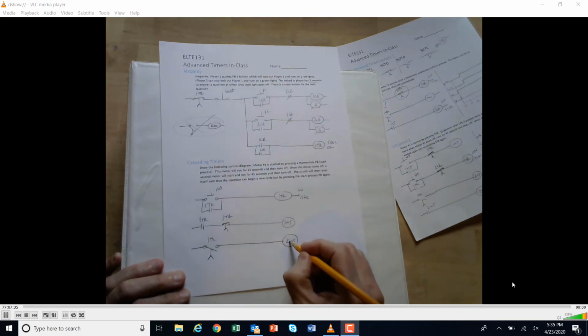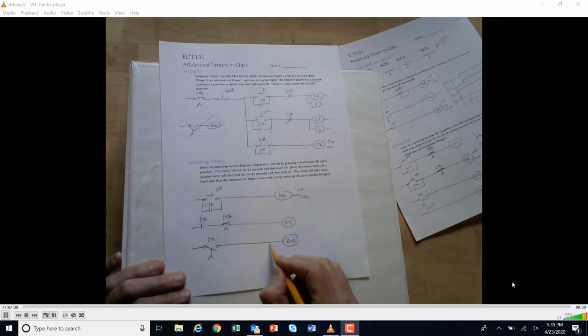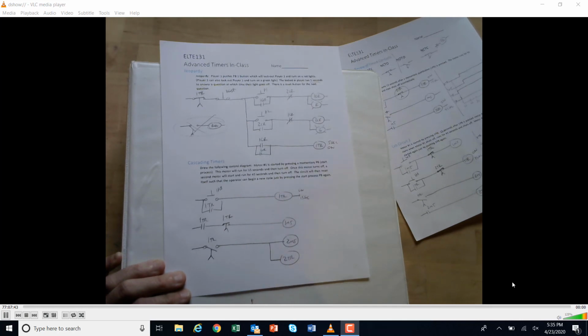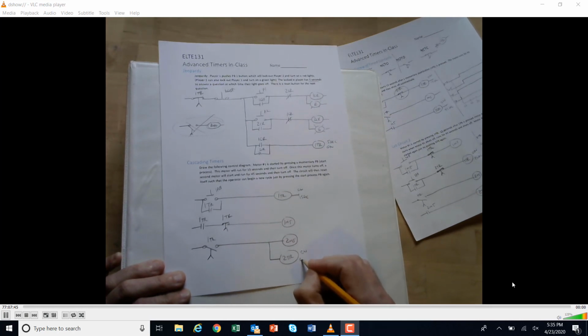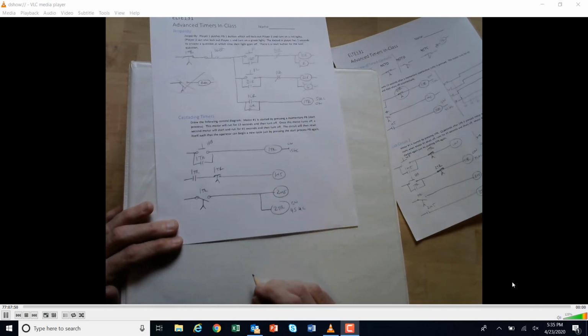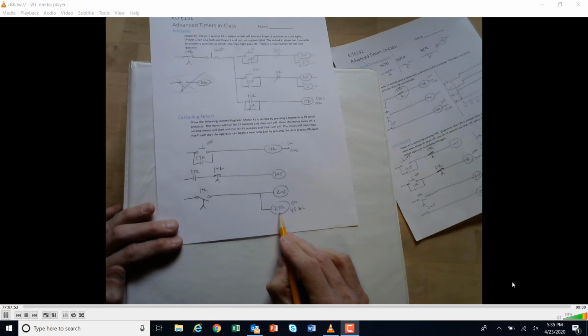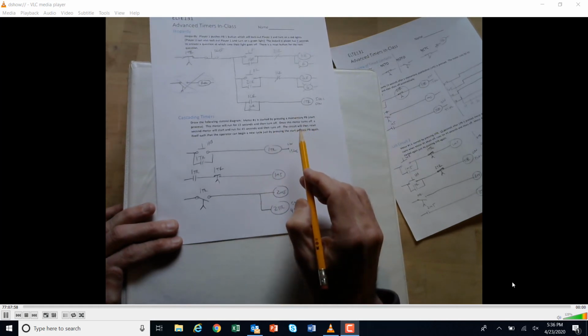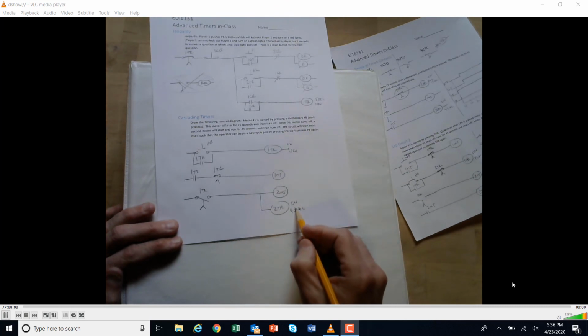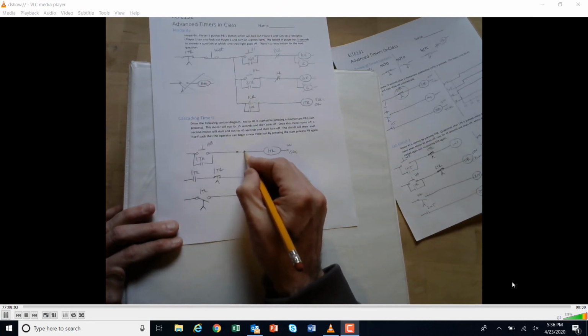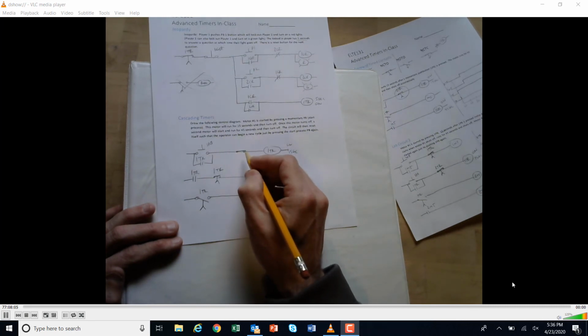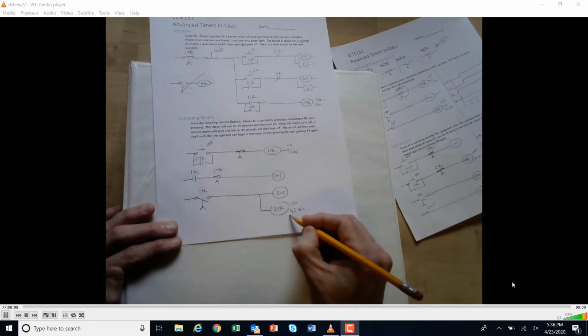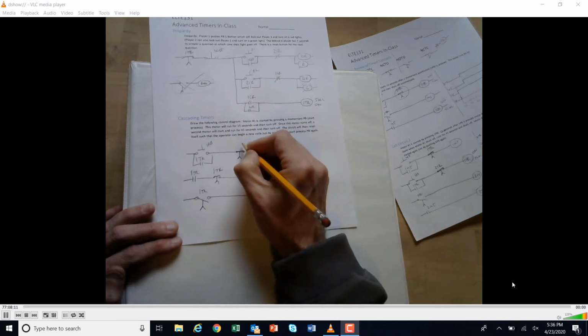Well, before we were having the second motor starter start the next timer, we could actually just run this in parallel if we wanted to. And do another timer like this. Could have been an on delay, 45 seconds, right? And then what? Can you figure out where this goes? After 45 seconds, it will turn everything off. Okay? Well, we take it up to the very top rung here, and we have it normally closed, and we time it open at 45 seconds.